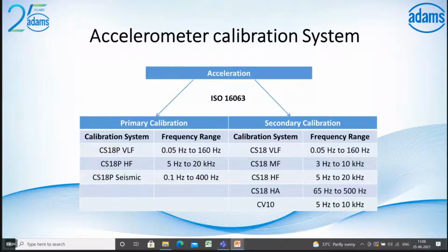First we'll start with accelerometer calibration. According to ISO standard 16063, it's a method for the calibration of vibration and shock transducers. Spectra is offering both primary and secondary calibration. Primary calibration systems include the CS18P VLF, for very low frequency from 0.05 Hertz to 160 Hertz, and the CS18P HF, a high frequency primary calibration system from 5 Hertz to 20 kilohertz. And the CS18P seismic covers 0.1 Hertz to 400 Hertz.